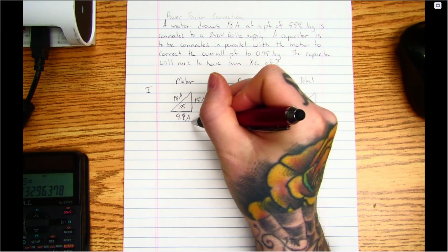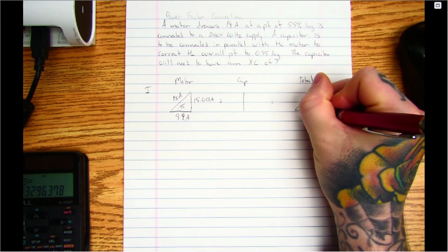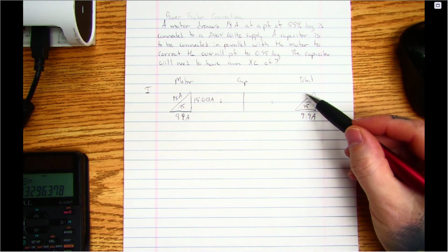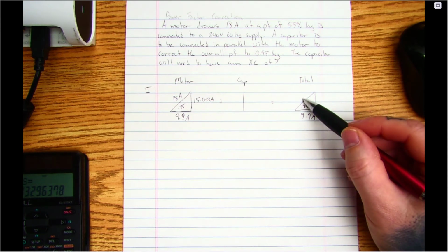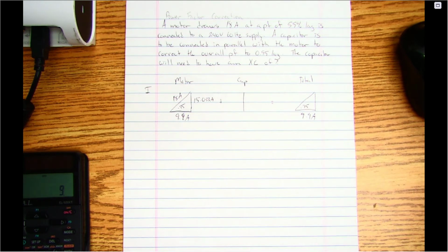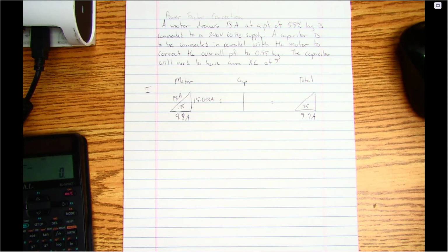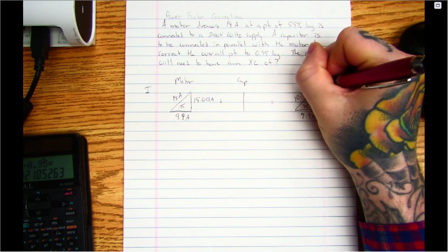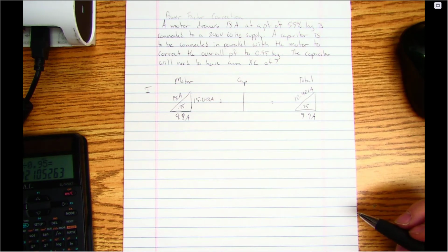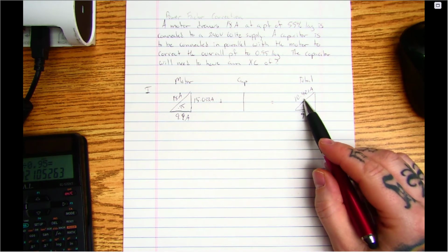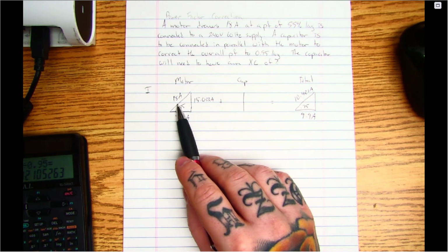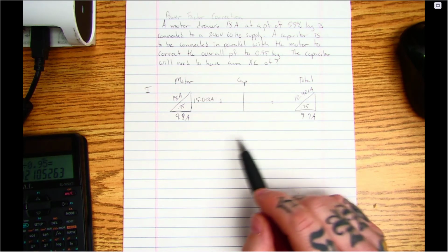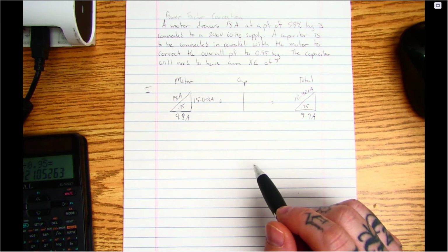So we can bring this guy right over to the bottom here and put 9.9 amps right there. Then I can solve for my new total line current. So I go 9.9 divided by 0.95 and I get 10.421 amps. Okay, so that's what the line current's going to be. So we can already see a difference. This motor's drawing 18 amps. Well, when we correct it to 0.95, the system is only going to have a 10 amp draw. So that's a significant amount of current difference.